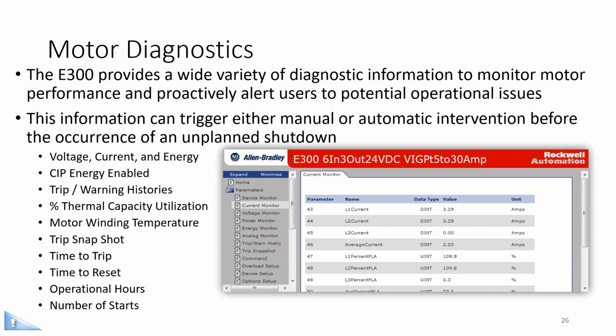Some popular ones are L1, L2, L3 average current, L1, L2, L3 average line voltage, ground fault current, power factors, energy, even energy demand, to really give you a sense of what's going on with your motor. The E300 continuously monitors and provides motor performance information. Users can monitor this information with a SCADA system to provide alarms and indicate motor performance to machine operators.